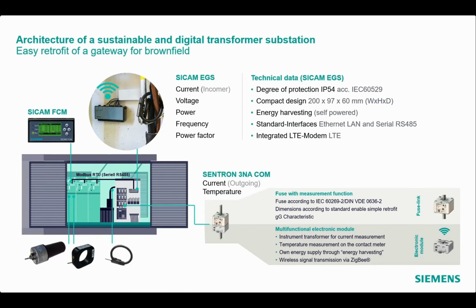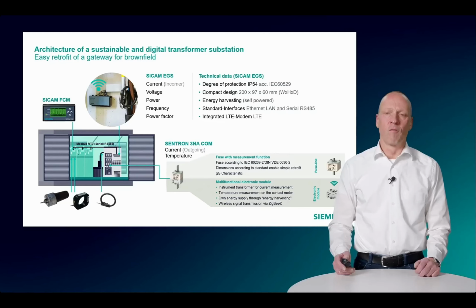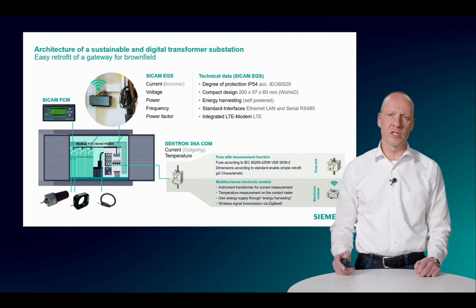I already mentioned that retrofitting of already existing conventional transformer substations towards digital transformer substations should be possible with minimized efforts. Especially for the brownfield application, we are providing a gateway called SICAM EGS, which means Enhanced Grid Sensor, and could easily be mounted somewhere on the LV side in a conventional substation. It comes along with 3 Rogowski coils, which can be installed on the secondary side of the distribution transformer to measure the main current on the low voltage side. The already mentioned smart fuses could also be easily retrofitted and connected via Zigbee to the EGS to provide the information about the outgoing currents. Voltage could be measured directly from the low voltage side with the EGS.